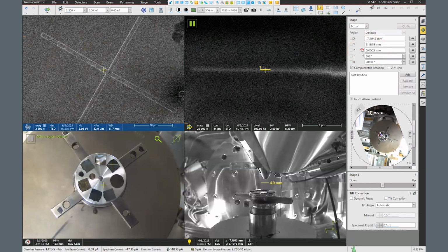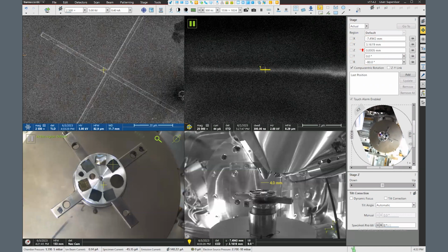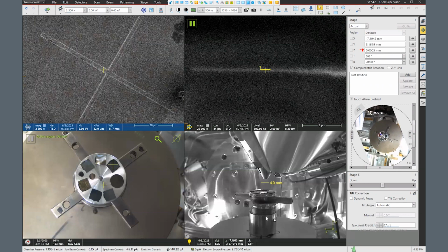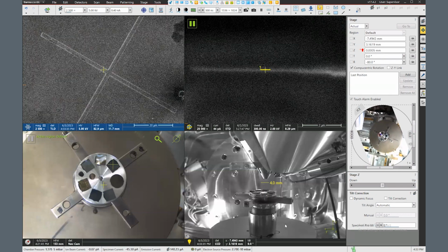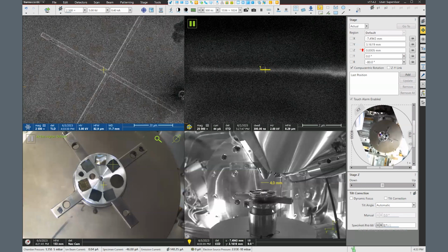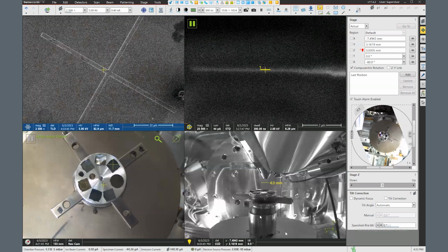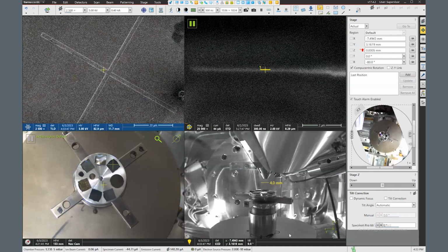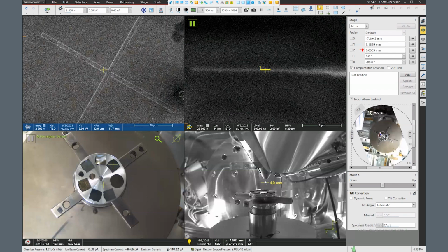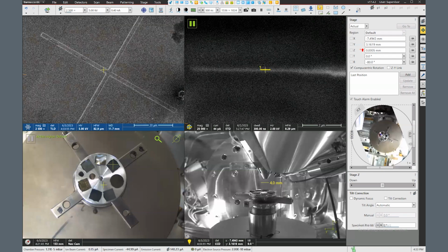And in this case, what it is is that the reference position for the stage is actually the main platter down here, because the system itself has no way of knowing how tall you've made the sample holder or how tall your sample is. So, you know, this could be almost down on the platter. It could be sticking up almost about to hit the pole piece. It really doesn't know based off the simple geometry of the system.